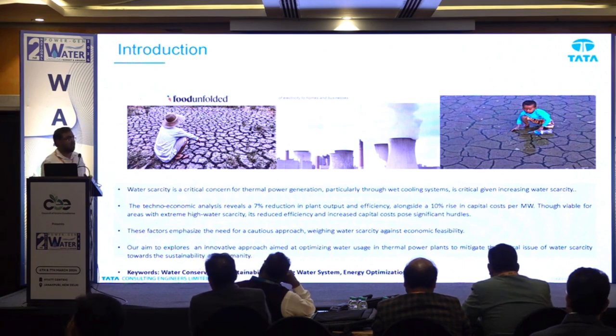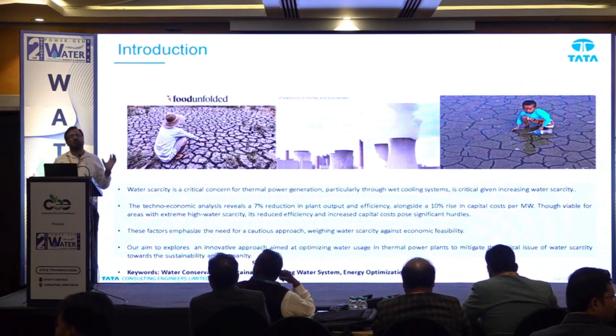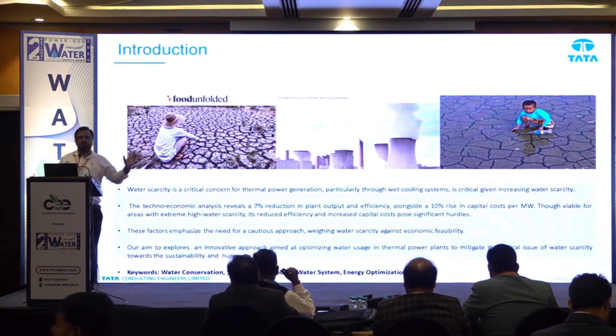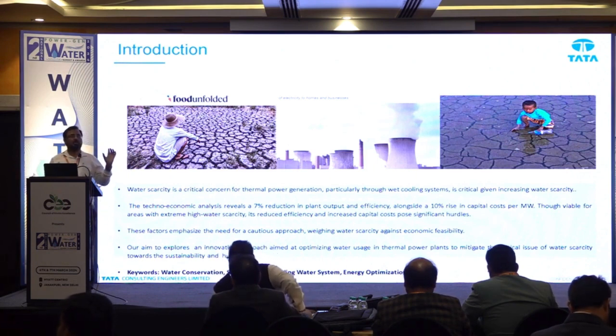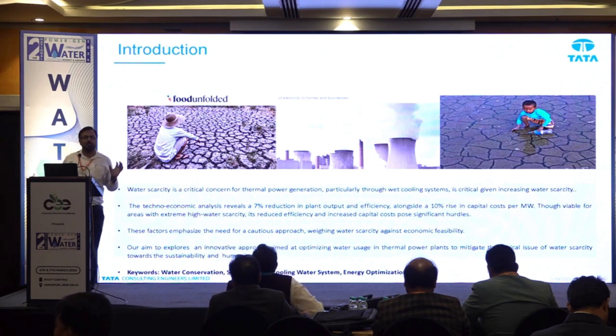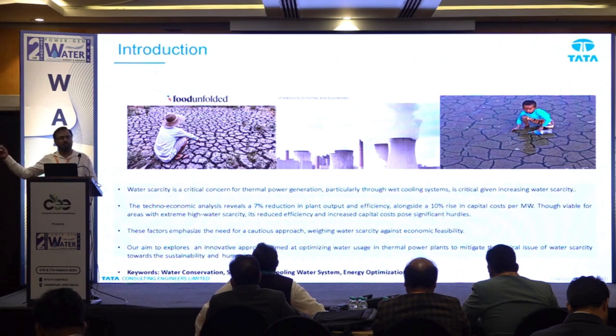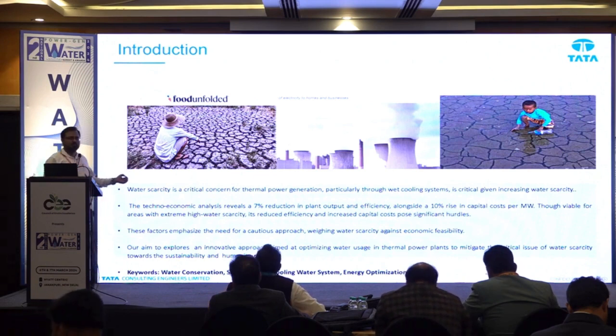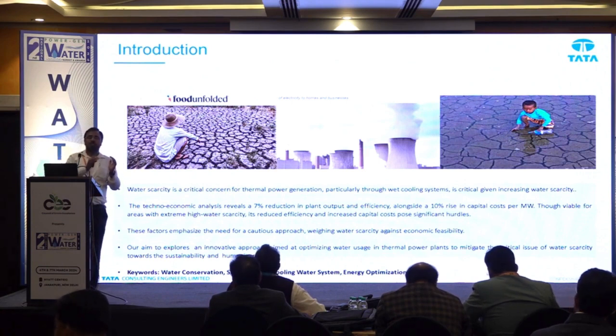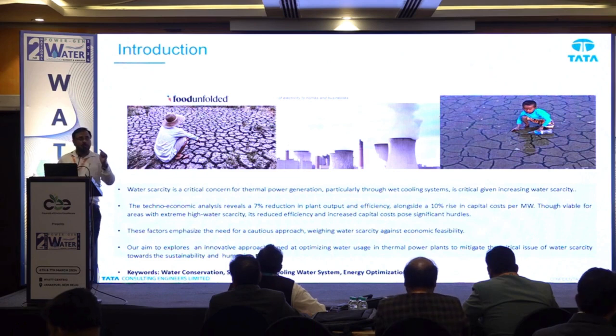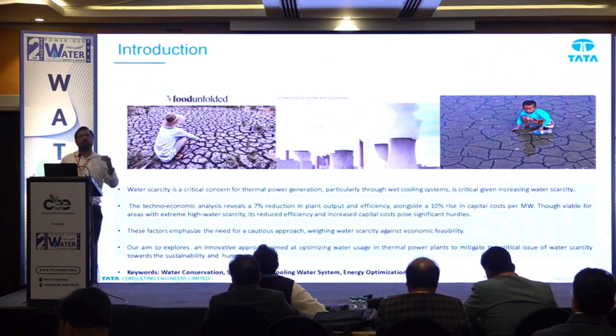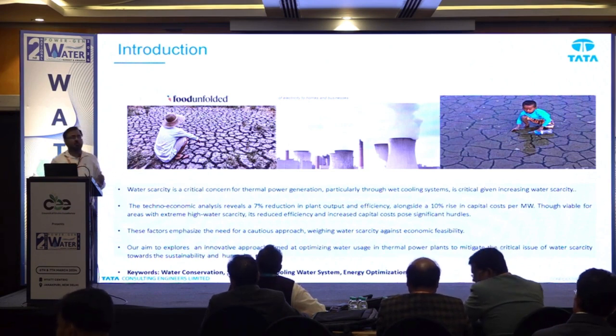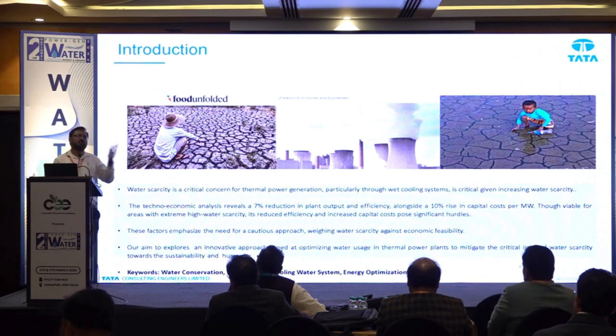Now, regarding what our previous honorable speaker told about water conservation in the main chunk area: for a project of 2 into 800 megawatts we are currently doing, the total intake is 3800, and out of that, you won't believe, makeup is 3200. 80 goes to city makeup, 80 to cycle makeup, potable makeup, some for service water, 101—but out of 3800, 3000 is going for makeup. And in that 3000 makeup, the main chunk is going for evaporation. Based on the evaporation quantity and the COC we maintain, the blowdown is determined.